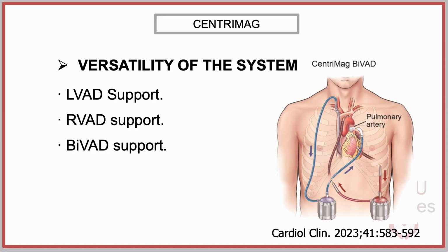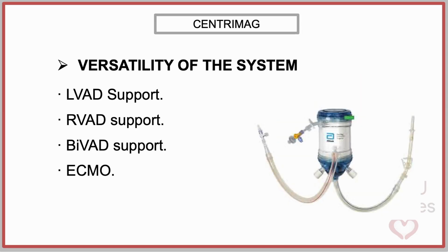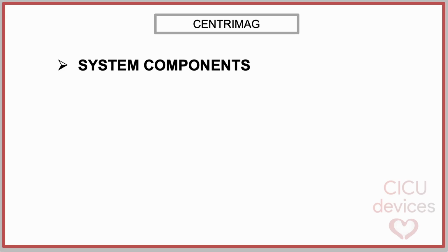Biventricular support can be established by combining the configurations described above. Finally, an ECMO configuration can be implemented by incorporating a membrane oxygenator into the circuit. This flexibility enables adaptation to a wide range of clinical scenarios without requiring significant changes in equipment. The CentriMag circulatory support system consists of several integrated elements. The main components include the disposable centrifugal blood pump.